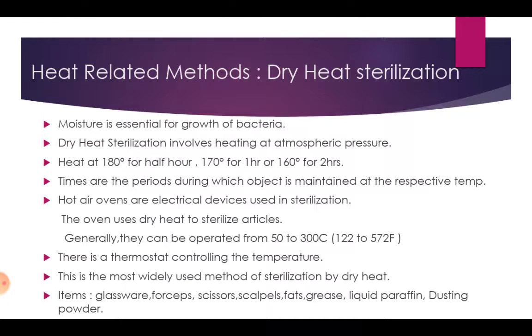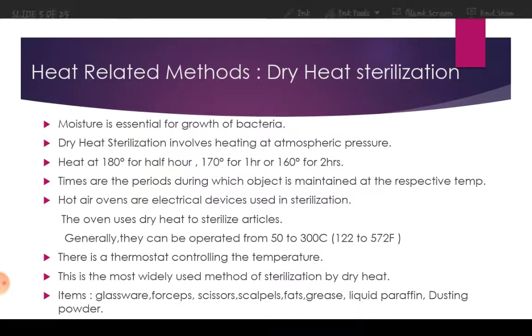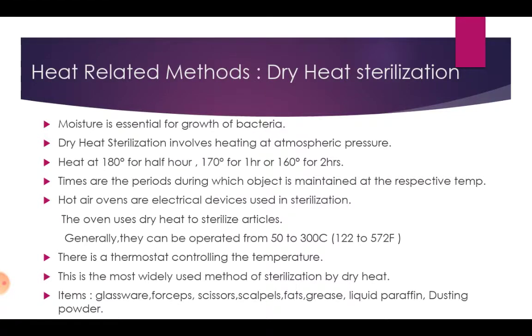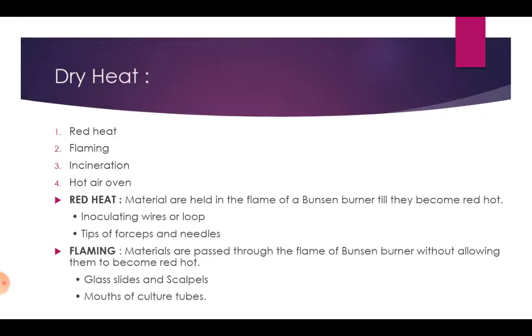Hot air ovens are electrical devices used in sterilization. The oven uses dry heat to sterilize articles. Generally, they can be operated from 50 to 300 degrees Celsius and 122 to 572 Fahrenheit. There is a thermostat controlling the temperature. This is the most widely used method of sterilization by dry heat. Items: glassware, forceps, scissors, scalpels, fats, grease, liquid paraffin, dusting powder.